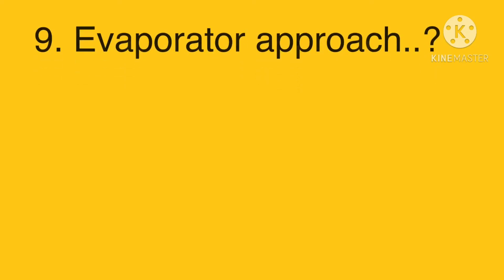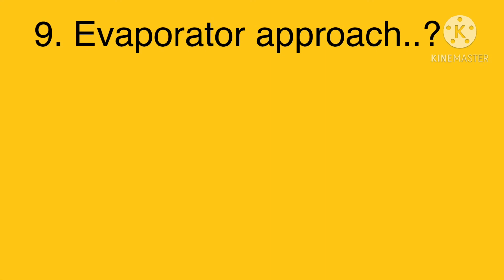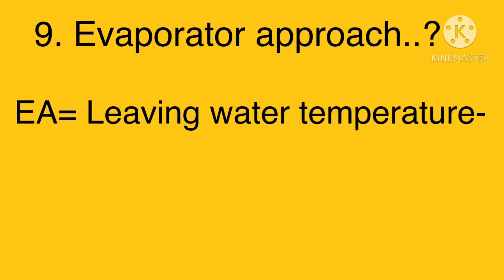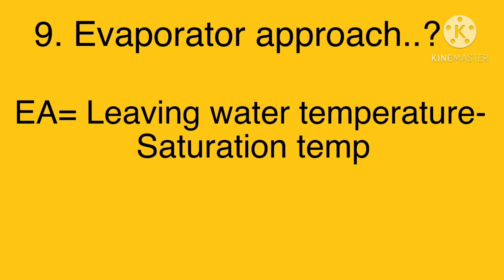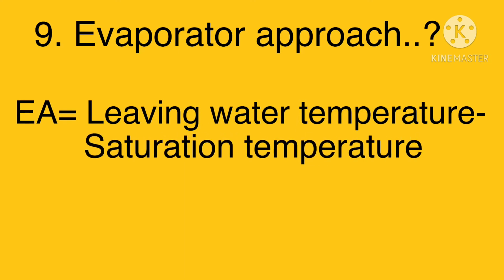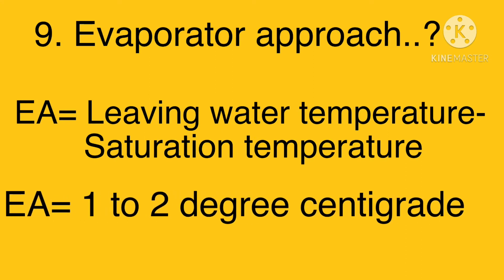What is evaporator approach? Evaporator approach, EA, is equal to leaving water temperature minus saturation temperature. Here the EA range is around 1 to 2 degrees centigrade, from a safe and economical point of view. If it goes beyond this value, scale formation results and the cooling efficiency of the chiller system may be reduced.